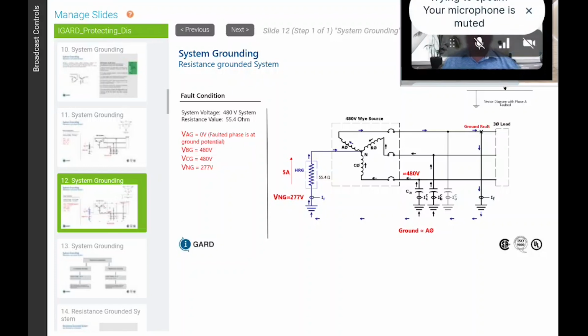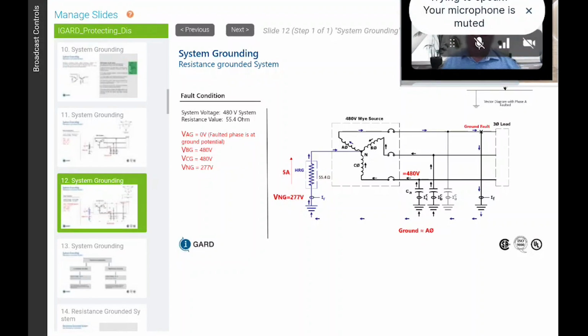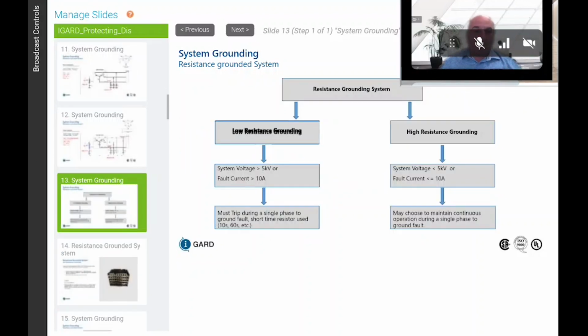We annunciate the alarm. There's another path of ground fault current going through the capacitive coupling of your system, and that can be as high as 5 amps. But in a 480 volt system, in our experience, I've never witnessed more than 1 amp in any size transformer.